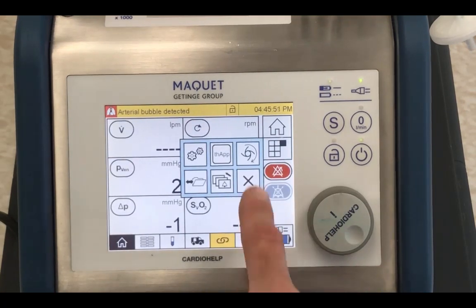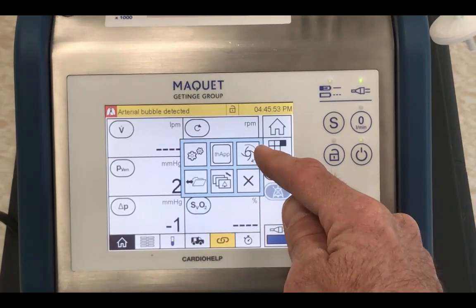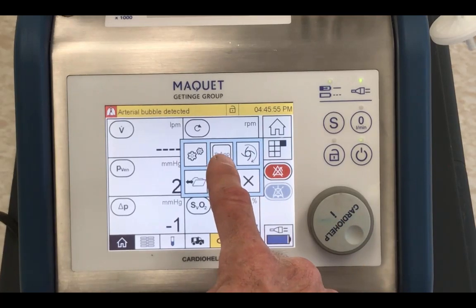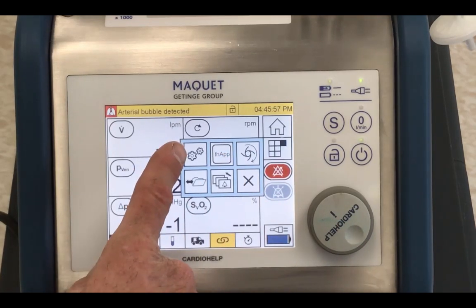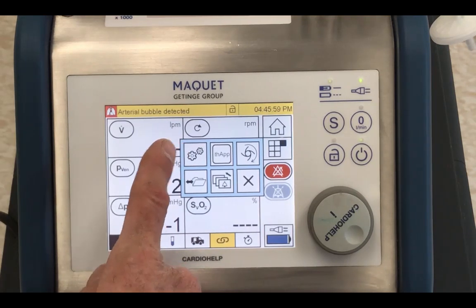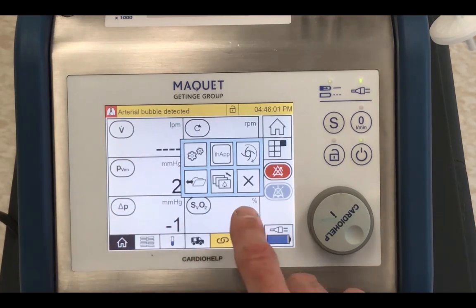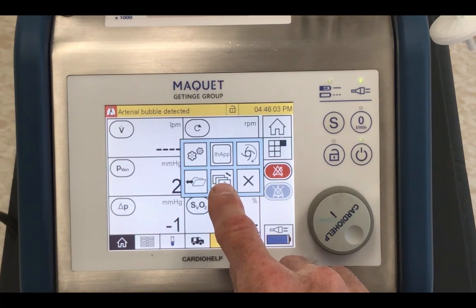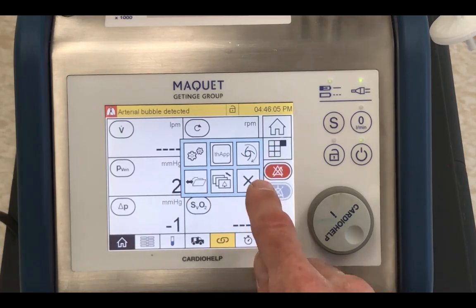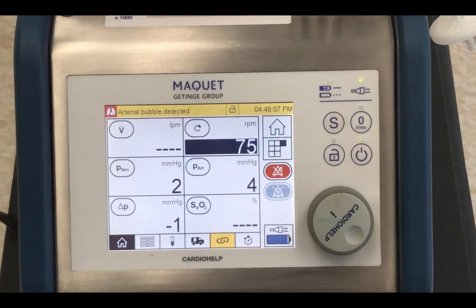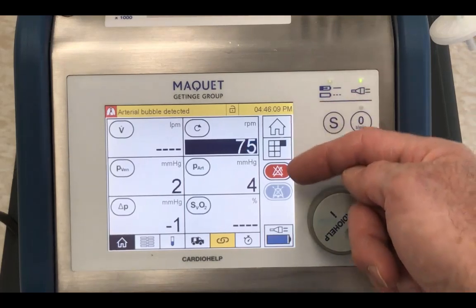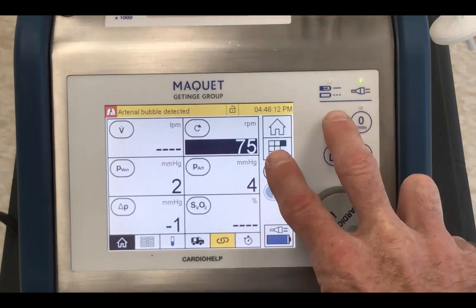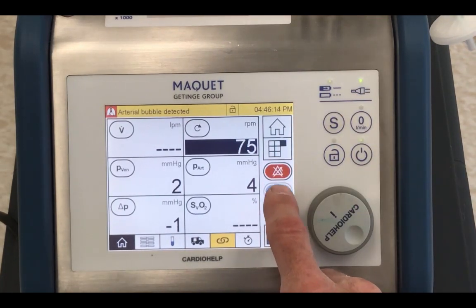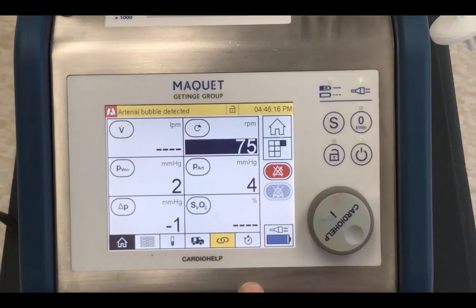Back into Tetris, we've worked our way around. There's the pump, LPM versus RPM. Pick your 2 of 5 therapy applications, change the date and time and the brightness and the loudness, turn your data on and off, and look at the alarm history. The X closes the Tetris window. We've already come down and shown you how to do a global override with 2 buttons here, and this is your typical silence alarm there. A little blank space, nothing goes in there, and this is your battery function.